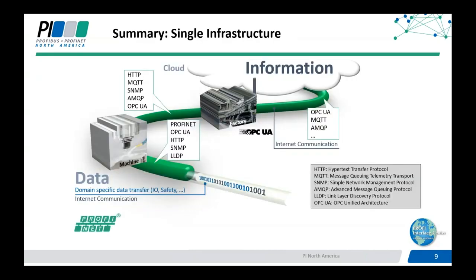In conclusion, PROFINET uses those three communication channels to be able to transmit data efficiently and with the required speed and determinism. But most importantly, other protocols can also coexist in this single infrastructure with PROFINET. Since PROFINET is based on standard and modified Ethernet, we also have the capacity to have other Ethernet protocols running on the same wire, on the same network.